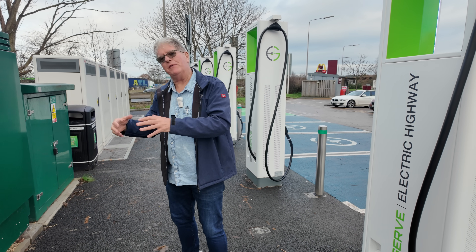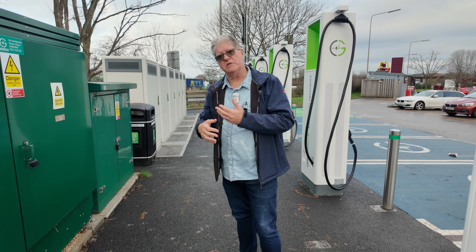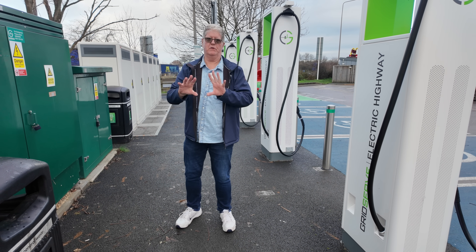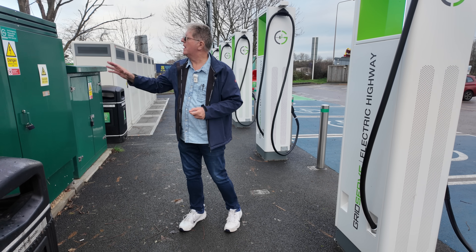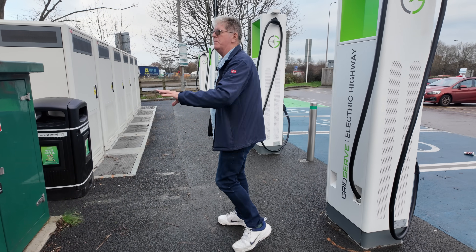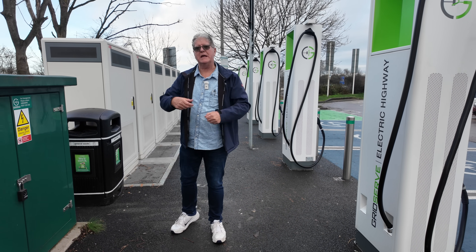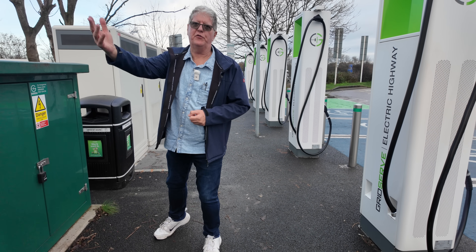Most people before the advent of public EV chargers chose 415. When you come onto chargers, it's very different. These here for GridServe are saying 400 volts. When you go to a Tesla Supercharger, they set the switch inside to 480 volts - every one, they're all the same. Tesla, for some reason, do like to have a higher voltage coming into the site. So that's the power that goes through to the cabinet. This is normally the communications cabinet. GridServe wants to know which charger is being used, if any are broken, who's using it, who's charging. And more importantly, when you swipe a contactless card, it's normally inside here that sends the signal through to GridServe so they can collect their money. We've got on the back of this one some sort of wireless receiver, and there'll also be a hardwired internet connection inside. This allows GridServe to monitor the chargers, monitor the usage, monitor the people actually charging, and then collect the money at the appropriate time.